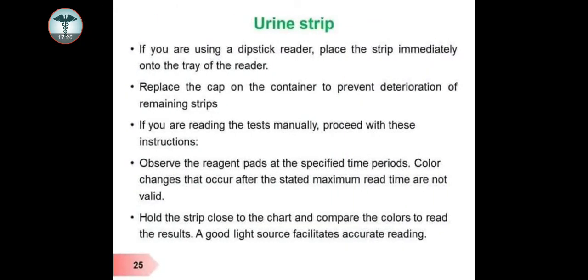If you are using a dipstick reader, place the strip immediately onto the tray of the reader. Replace the cap on the container to prevent deterioration of the remaining strips. If you are reading the test manually, proceed with these instructions. Observe the reagent pad at the specified time period. Color changes that occur after the stated maximum read time are not valid. Hold the strip close to the chart and compare the color to read the result.